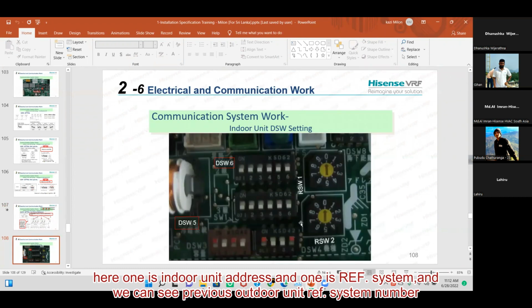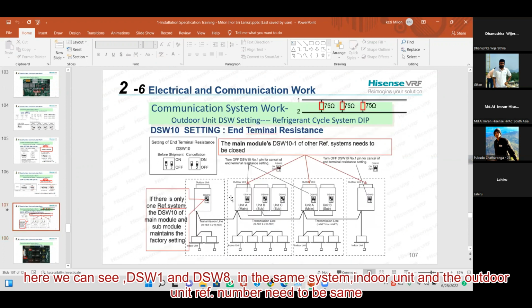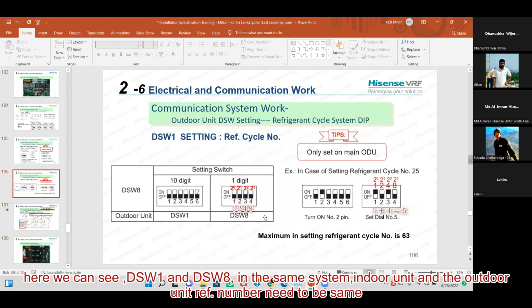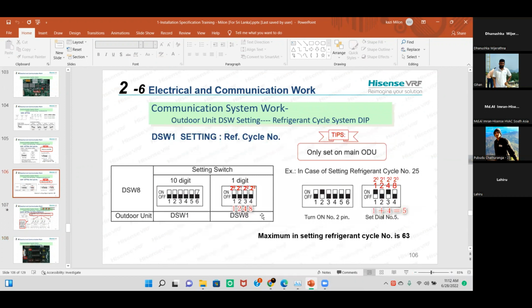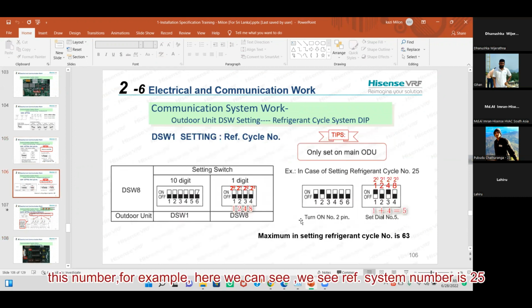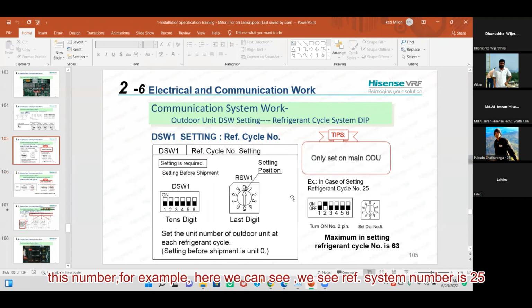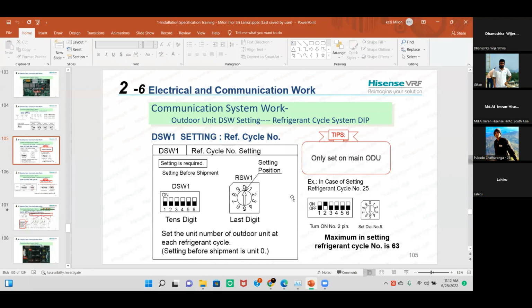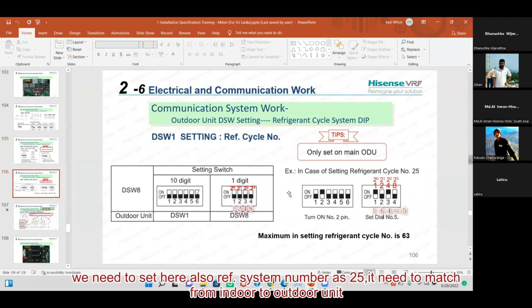One is the indoor unit address and one is the refrigerant system address. We can see previously here DSW1, for the same number. For example, here we set the refrigerant system number to 25. We need to set here also the refrigerant system number to 25. It needs to match from indoor to outdoor unit.